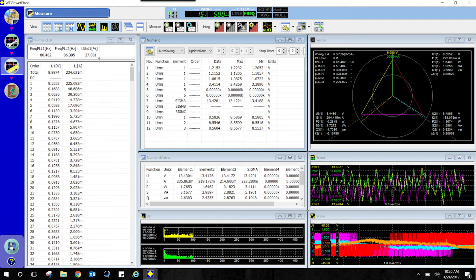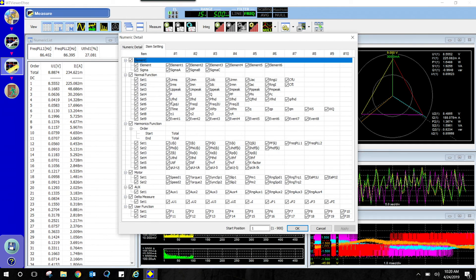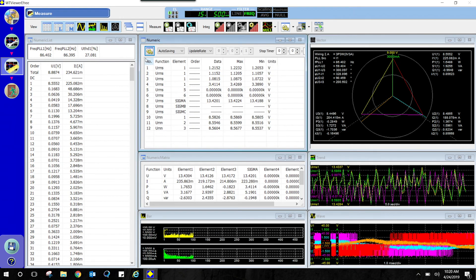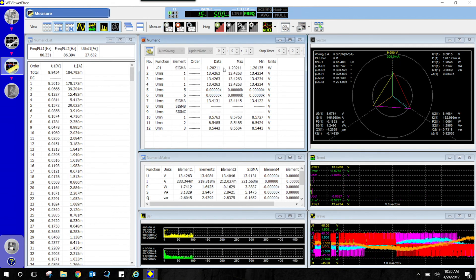Once in the measure display, we will select the Numeric Item button and make sure that the delta measure box is checked. We can then select one of our function drop-down boxes to select the delta P option from our function list. Be sure that the element group selected is the one we have our three-phase system on. As we can see, the delta P values are being collected.